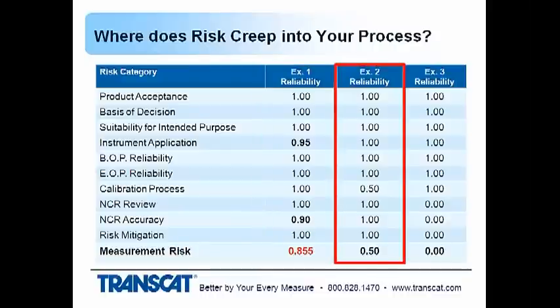In the next example, example 2, everything is good except for the calibration process where, for example, half of the test points were checked, based on where the instrument is being used and how it's being used in the process. So if you didn't check all of the functions or all of the ranges of an instrument where it's being used, you've lost traceability in your measurement. You have no idea about the confidence of your measurement. So let's say half of those are being checked, you give that a value of 50%. Overall, it drops to 50%.